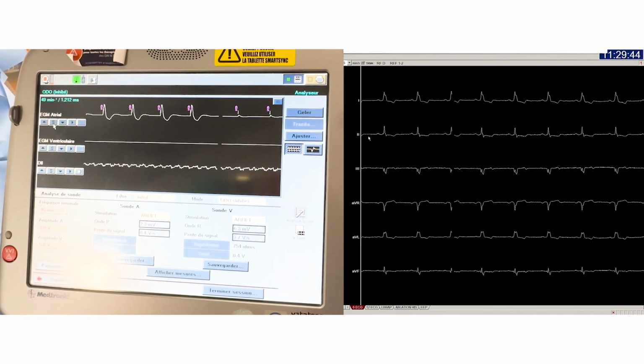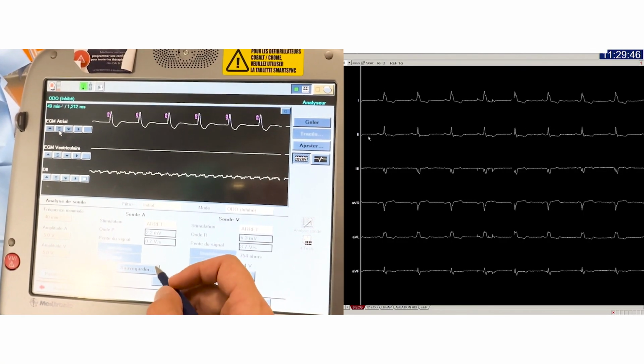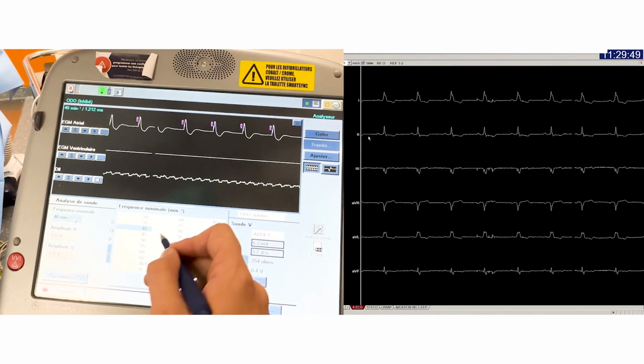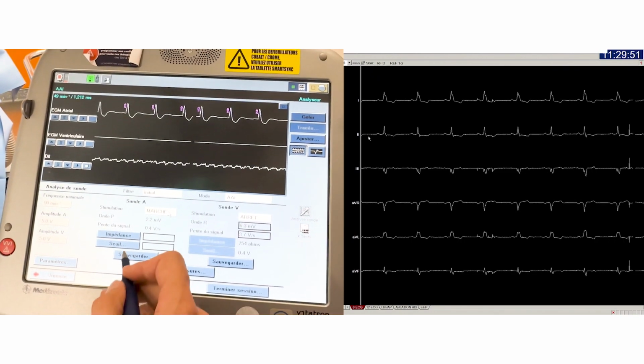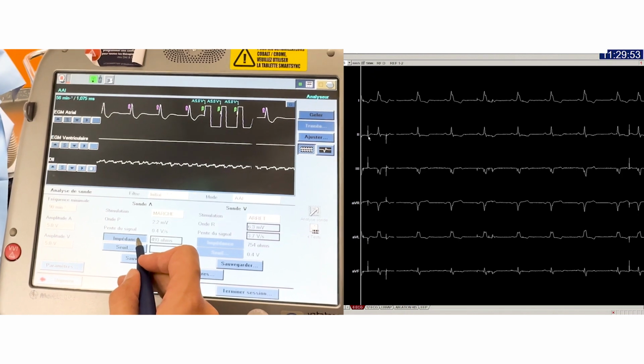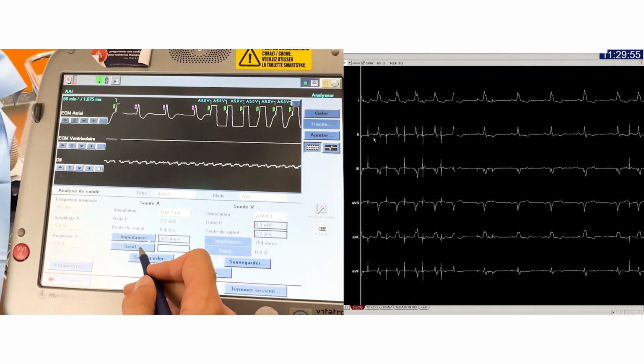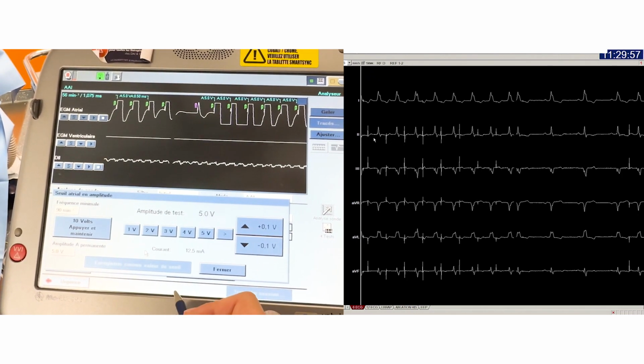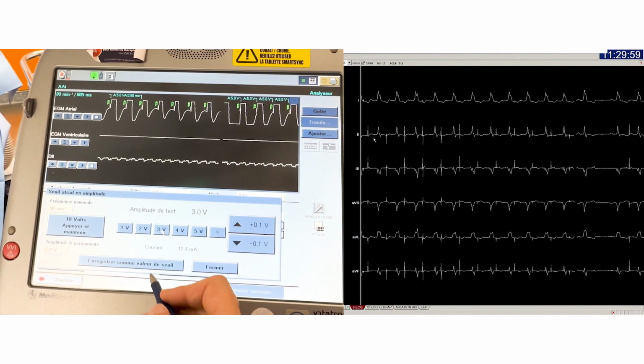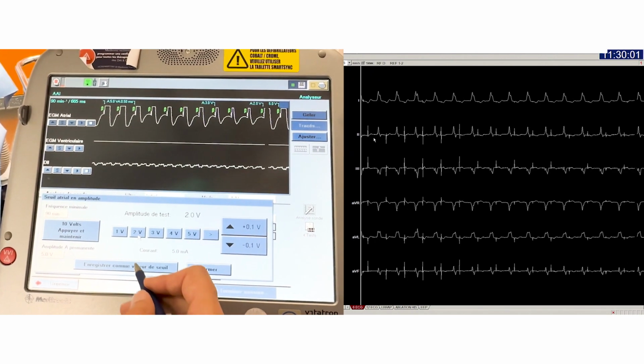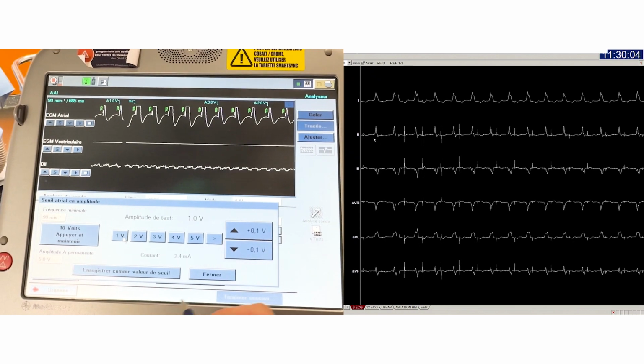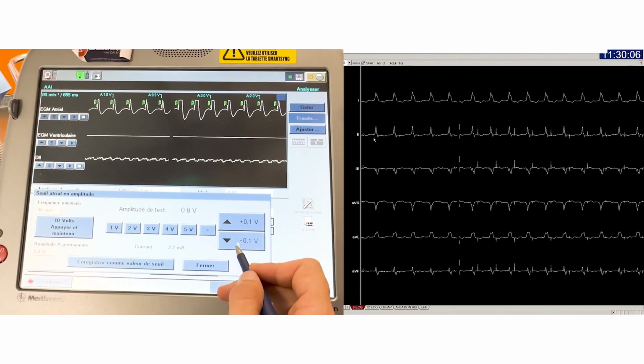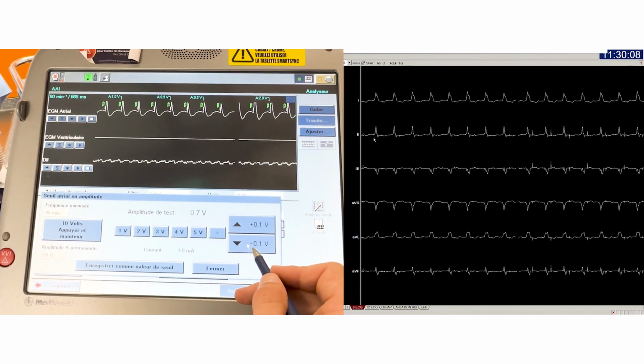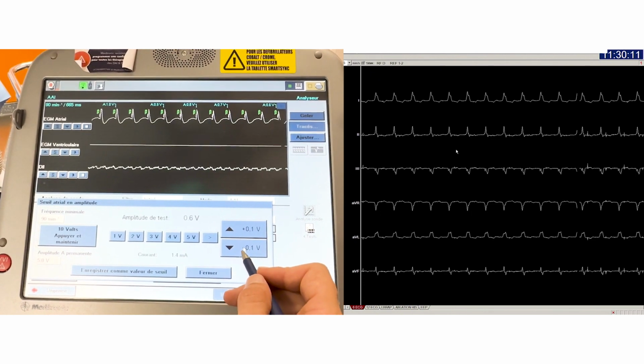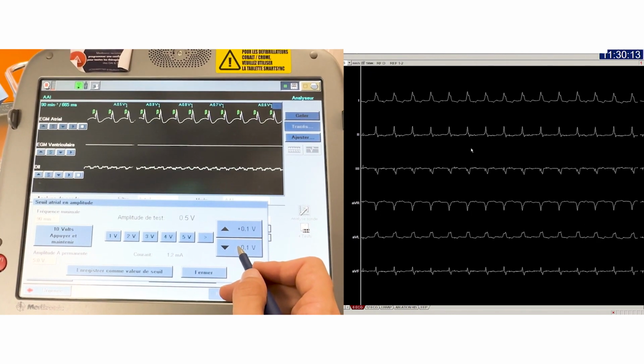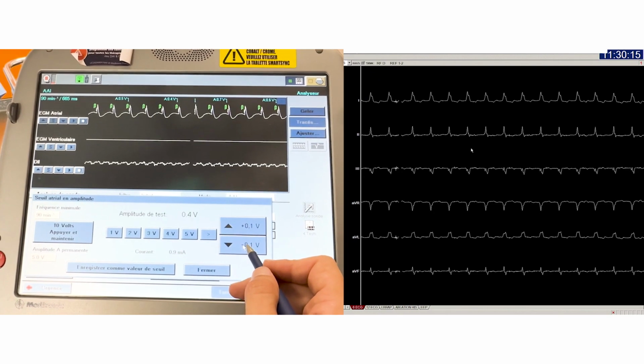The lead senses atrial events at around 2.3 millivolts, and the impedance is around 500 ohms. We can confirm atrial capture by looking at the atrial EGM, but also on the 12-lead ECG, which shows P waves after every spike. The right atrial lead threshold is below 1 volt, which is excellent. 0.4 volts to be exact.